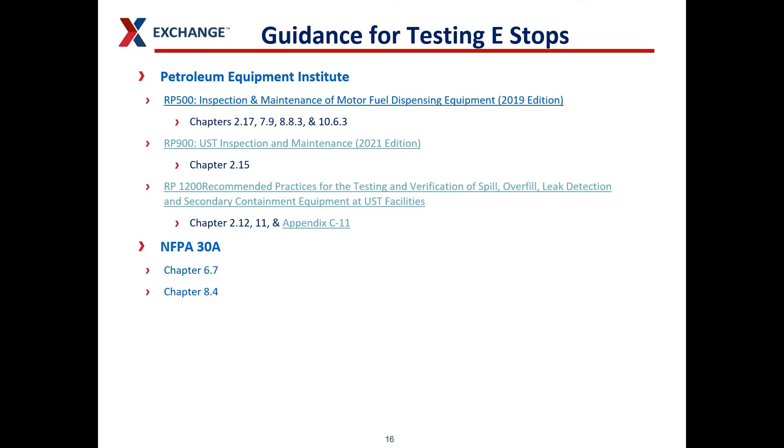We know it's common sense to test your equipment and make sure it works properly, but there are guidance documents out there for you to follow. The Petroleum Equipment Institute puts out three different guidances — the RP-500, RP-900, and RP-1200 — that all recommend testing your e-stops. The National Fire Protection Association also has guidance in Chapter 6.7 and Chapter 8.4 of NFPA 30A that tells you to test your e-stops and make sure they work properly.